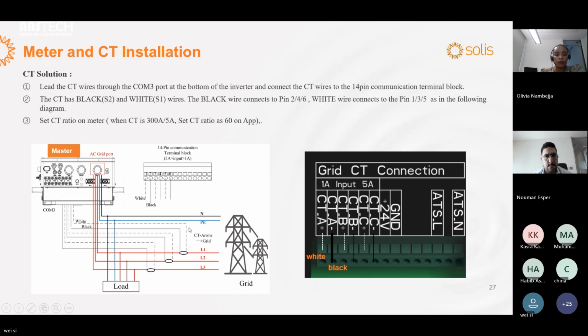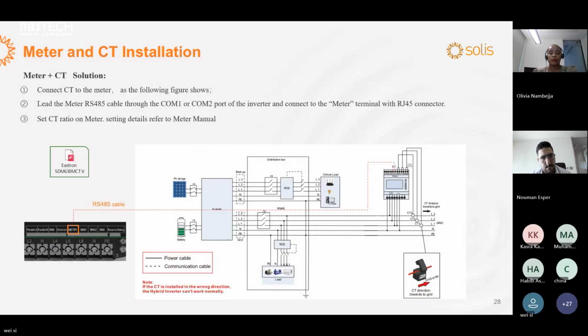About the CT solution, only CT in the system: just connect the simple wire to the inverter, and you should be careful not to connect to the wrong position on the onboard. The positive is the white cable, and the negative is the black cable. Okay, it is the meter and CT solution. You should connect the CT cable to the meter, then the meter connects to the meter port on the onboard inside the inverter.